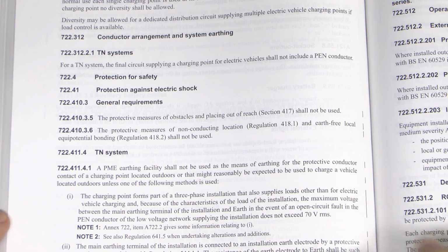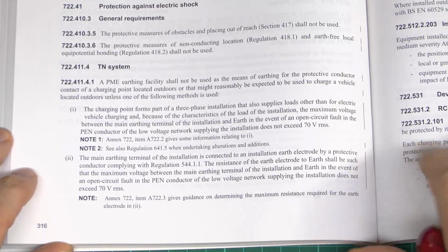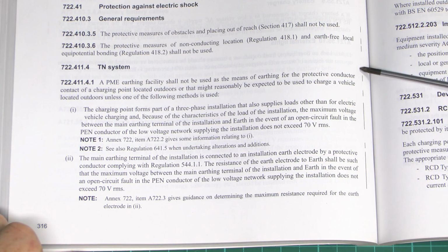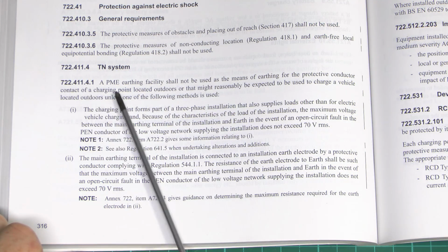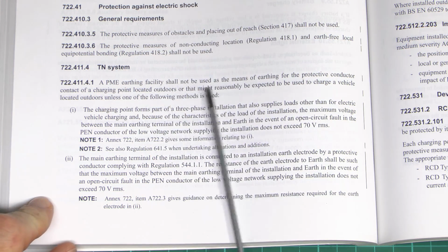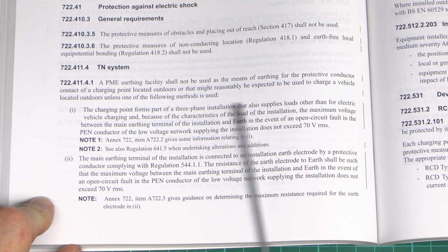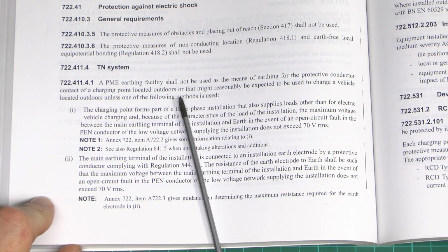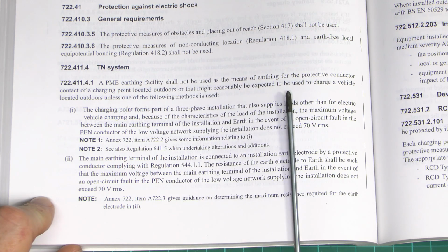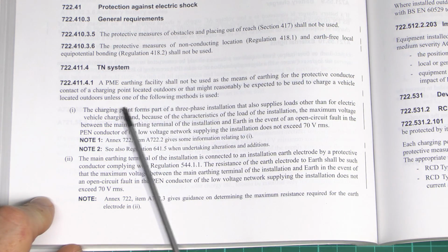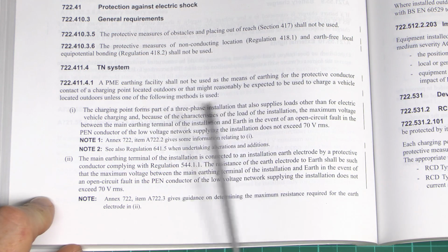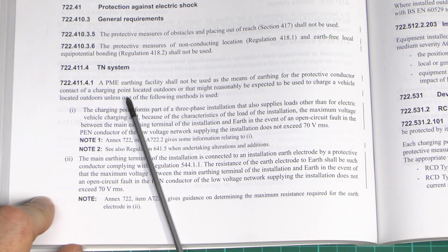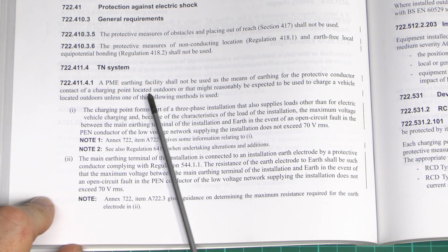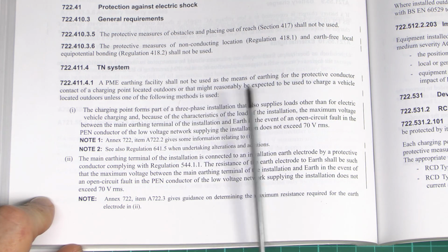But certainly for TNCS, then this is where things are going to be somewhat more problematic. So as we've got here, a PME earthing facility shall not be used as the means of earthing for the protective conductor contact of a charging point located outdoors, or that might reasonably be expected to be used to charge a vehicle located outdoors, unless one of the following methods is used. Now, 99% of vehicles are going to be charged when they're outdoors, and in fact most of the charging points are going to be outdoors, so very much it's going to be applicable there.